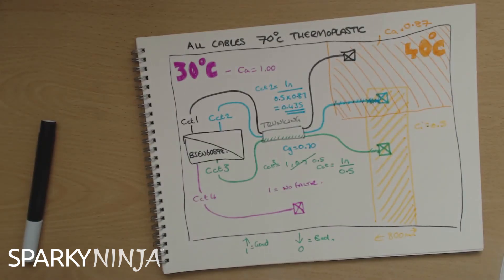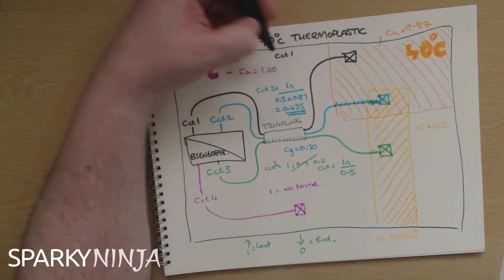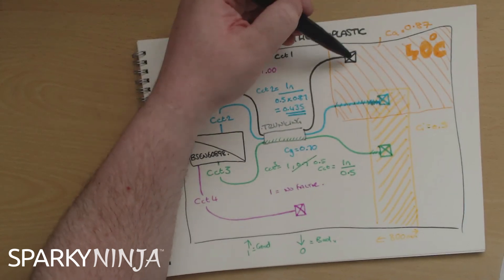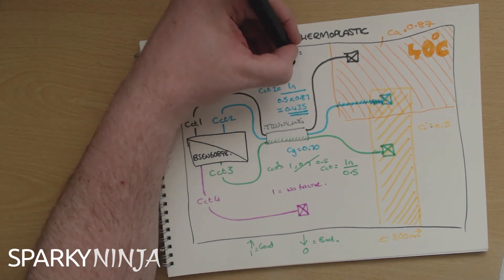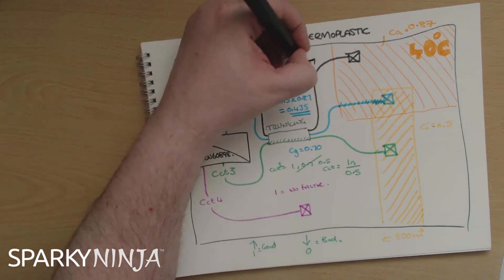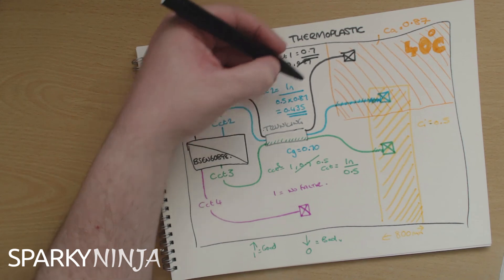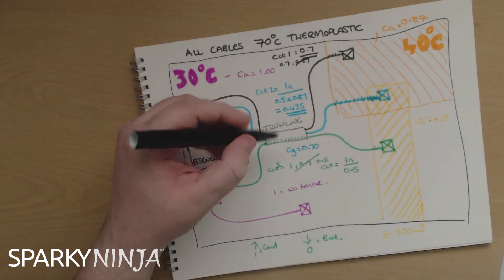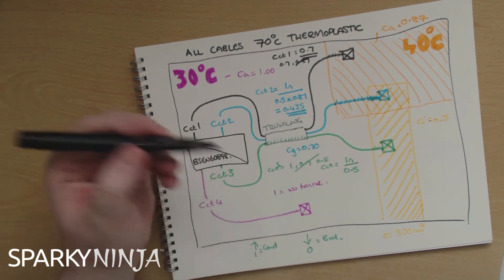For circuit one, I have the grouping factor of 0.7 and the temperature factor of 0.87. The cable in trunking is affected by grouping, and the cable connecting to equipment is in the higher ambient temperature — but these are separate sections, they don't coexist. So similar to circuit three, I pick the worst single factor, the one closest to zero: 0.7. Circuit one uses a factor of 0.7. Summary: circuit one uses 0.7, circuit two uses 0.435, circuit three uses 0.5, circuit four uses no factor.